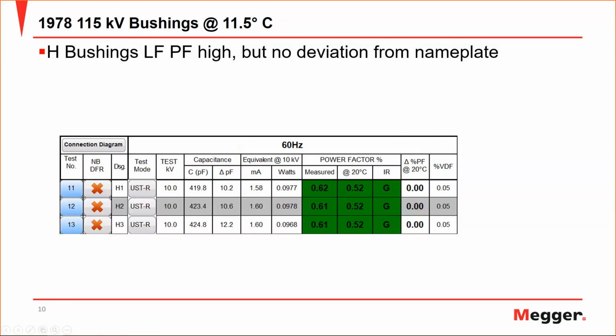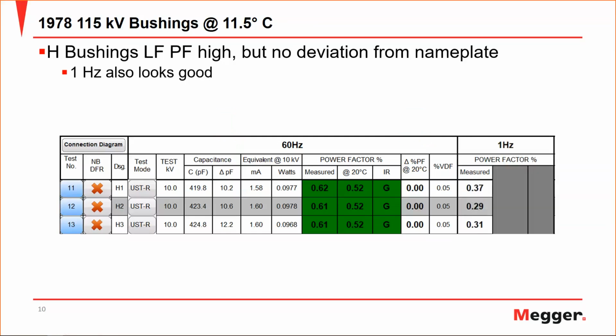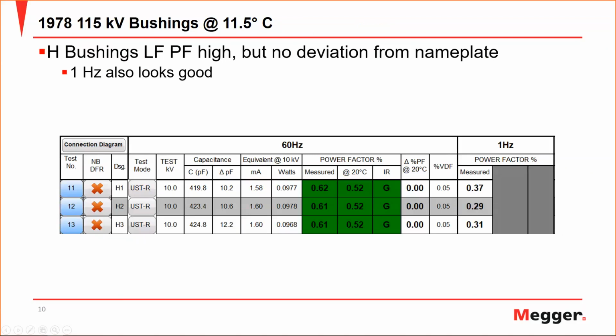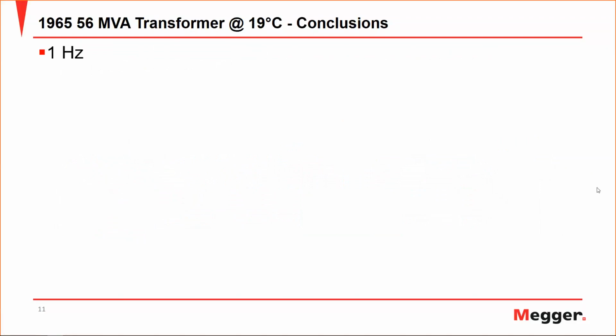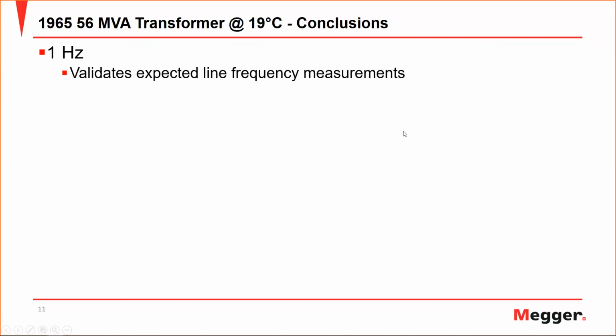But when we look at the 1 Hertz for this particular set of bushings, we can see that the values obtained are all relatively low themselves, and so there is no cause for concern. If you remember those graphs that Roberts was showing, for the assets that had high moisture or high oil conductivity, you saw the graph tend to trend upwards pretty steeply after 10 Hertz and go up at 1 Hertz. And that is how we are knowing if this 1 Hertz value is acceptable or not. So some conclusions for this transformer is that 1 Hertz validates the expected line frequency measurements.